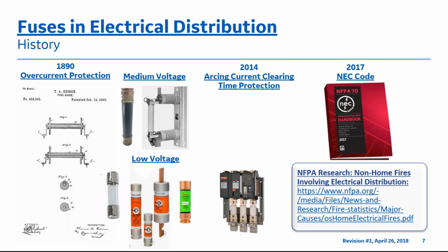The first statistic comes from the NFPA website link provided on this slide on the right-hand side. Please refer to page 99 of the NFPA PDF, Table 8.A, non-home fires involving electrical distribution equipment or lighting. In the time period of 2010 to 2014 of the annual averages, wiring and related equipment equal to 59% of those fires. And transformers and power supplies also equated to 13% of those fires. So adding the two numbers for wiring, transformers, and power supplies, which accounted for 72% of the fires during this 4-year time period.